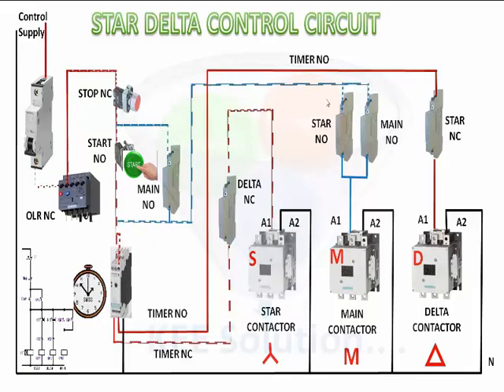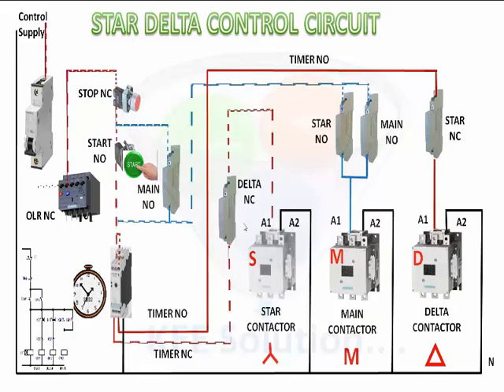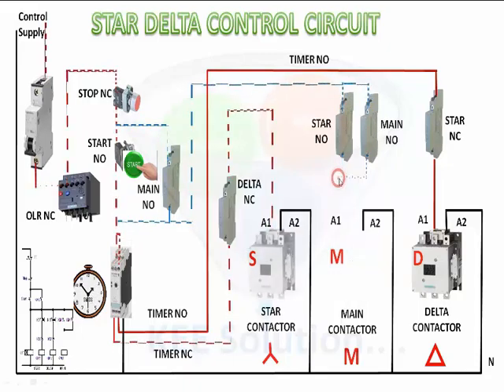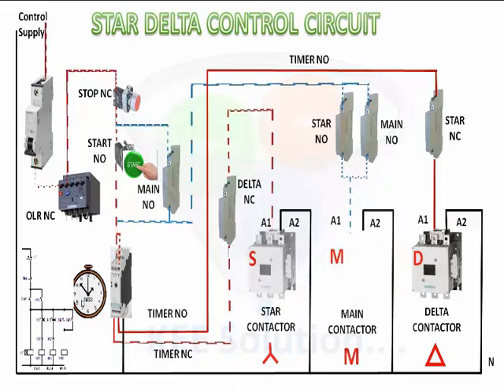Observe carefully: the power will go through the timer NC and delta contact NC to the star contactor. The star contactor will actuate first and after that all other functions will work. The power will go through start NO to star NO and the main contactor will also actuate.